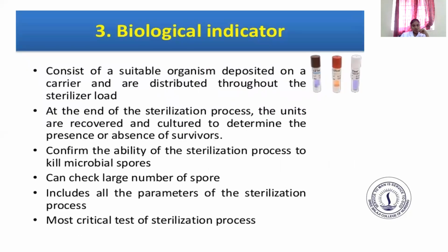And then third one, biological indicator, consists of a suitable organism deposited on a carrier and distributed through the sterilization load. At the end of the sterilization process, the units are recovered and cultured to determine the presence or absence of survivors. Confirms the ability of the sterilization process to kill microbial spores. Can check large number of spores. Includes all the parameters of the sterilization process. Most critical test of sterilization process.